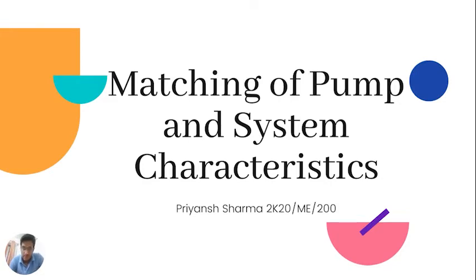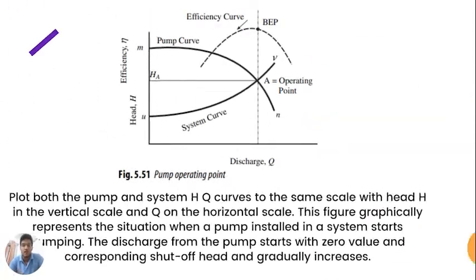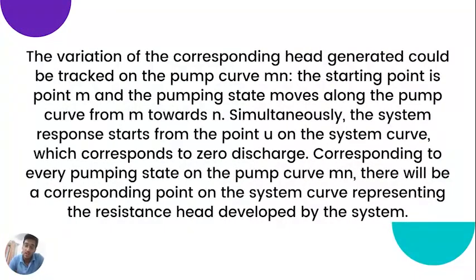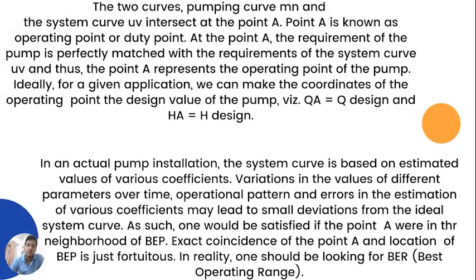My name is Priyan Sharma and my roll number is 2K20ME200. My topic is matching of pump and system characteristics. We need to plot the system and pump curve on a graph with x-axis representing discharge Q and y-axis representing head H. The figure represents the situation where the pump installed in a system just starts to pump discharge from zero. The variation in head can be noted by observing curve MN. There will be a point A where curve MN and curve UV intersect — this point is also known as the operating point of the pump. A pump should be selected such that its best efficiency point (BEP) coincides with point A for achieving the ideal operating case.